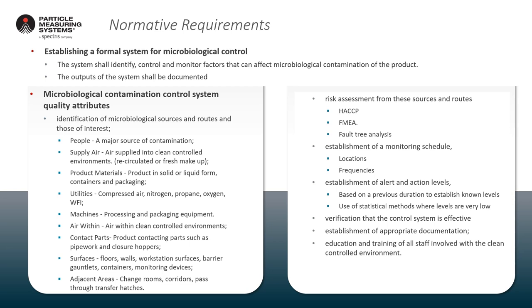The normative requirements define what's required in establishing a formal system for microbiological control. This includes defining the microbiological contamination control system's quality attributes, the identification of microbial sources and routes of interest, risk assessment to see how those sources are generated and their routes into critical areas, the establishment of a monitoring schedule, the establishment of alert and action levels, verification that control systems are effective, and ensuring documentation, education and training is performed.